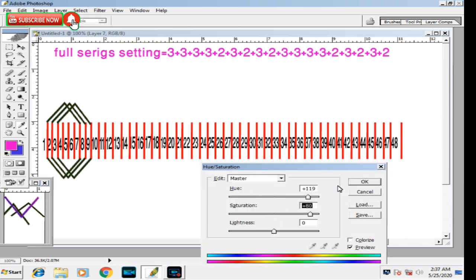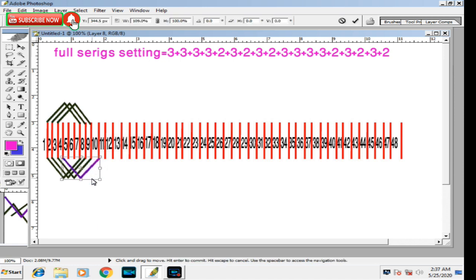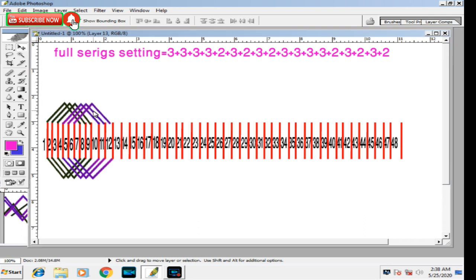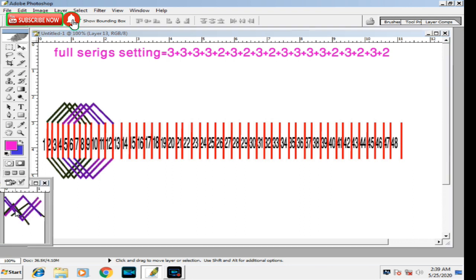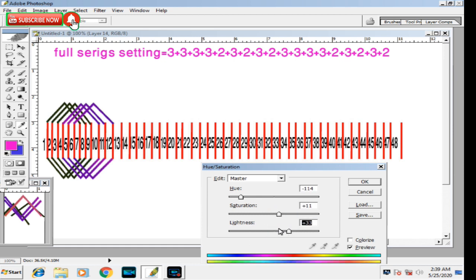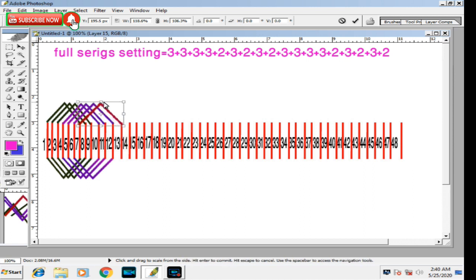This formula applies to any 48-slot motor. Any 48-slot motor at 900–916 RPM uses this system. This is the only system for a 48-slot motor at 900 RPM — no other system. Per slot, two coils each. Now two series is complete. Now, three coils in another series.